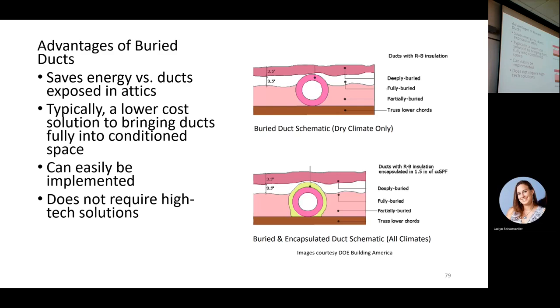So the 2018 code, which we did not adopt, actually talks about this and has recognized the value of burying it in the insulation. And we can see the diagram on the upper right, and they are giving us a couple of options, and they have what's partially buried where the top's exposed, and then fully buried where the insulation comes right to the top of the duct, and then deeply buried where you completely bury it. It takes effort on the HVAC guy's part to make sure he installs the ductwork so it's down low.